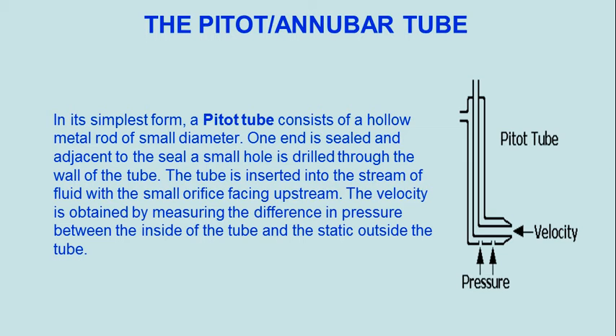In its simplest form, a pitot tube consists of a hollow metal rod of small diameter. One end is sealed, and adjacent to the seal, a small hole is drilled through the wall of the tube. The tube is inserted into the stream of fluid with the small orifice facing upstream. The velocity is obtained by measuring the difference in pressure between the inside of the tube and the static pressure outside the tube.